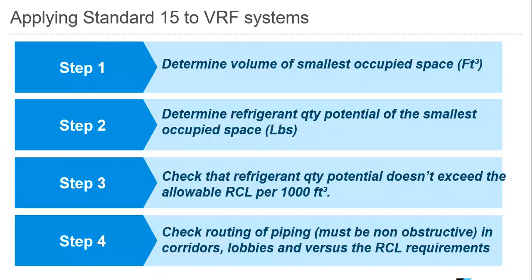So when we apply ASHRAE 15 to VRF systems, we go through 4 different steps. We want to determine the volume of the smallest occupied space. Next, we want to determine the refrigerant quantity potential of the smallest occupied space. Next, after that, we want to check that the refrigerant quantity potential does not exceed the allowable RCL, or refrigerant concentration limit, per 1,000 cubic feet. And then we want to check the routing of piping. It has to be non-obstructive within corridors, lobbies, versus the RCL requirements.